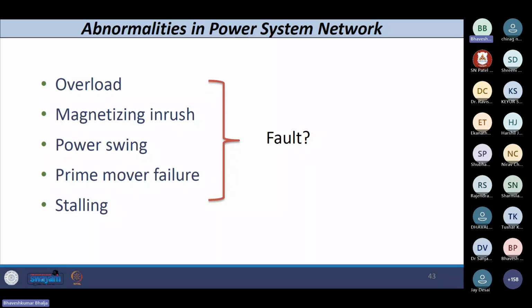That is no issue. But the issue comes with the turbine, because if any turbine fails, coal, hydro, or anything, and you do not take immediate action within a certain time limit, then the blades of the turbine may become corroded. So the blades of the turbine may get damaged. If you have a hydro turbine, bubbles or cavitations are formed. If you have diesel or some other generator, then a fire may happen because of unburned fuel. A similar situation occurs in the case of gas also. So this is not a fault again. This is a different phenomenon, so this needs to be discriminated.